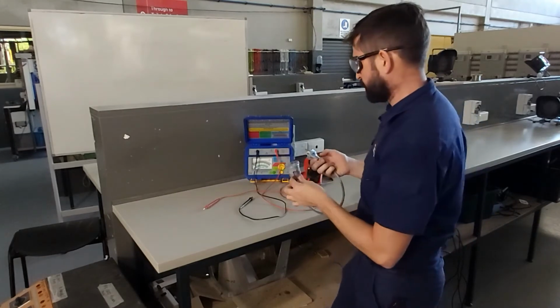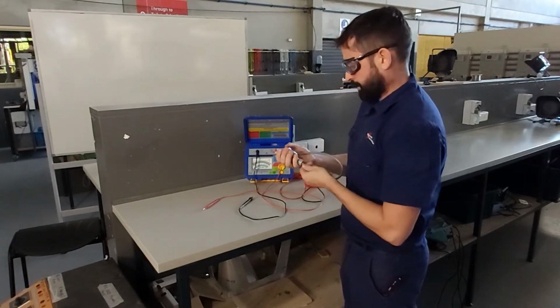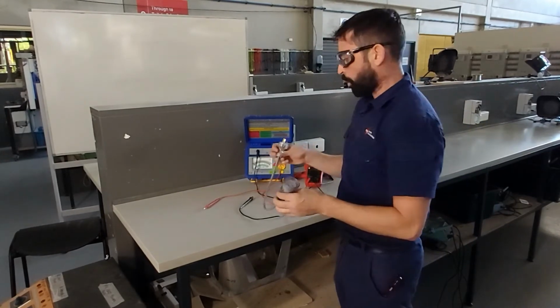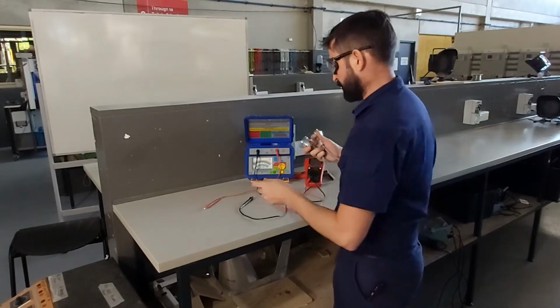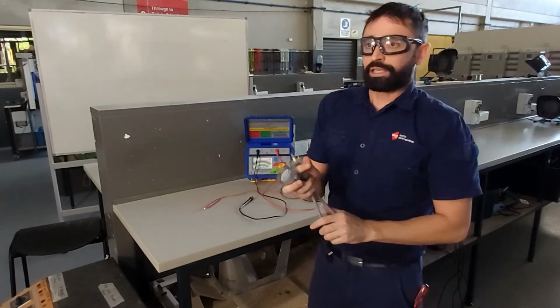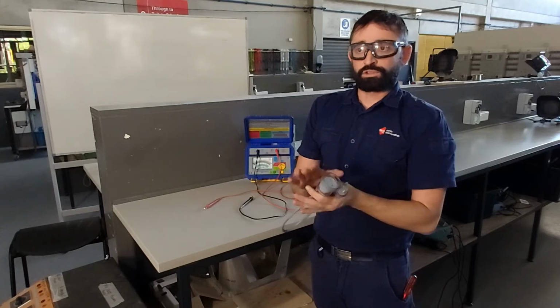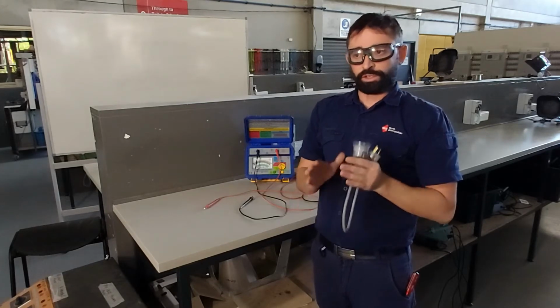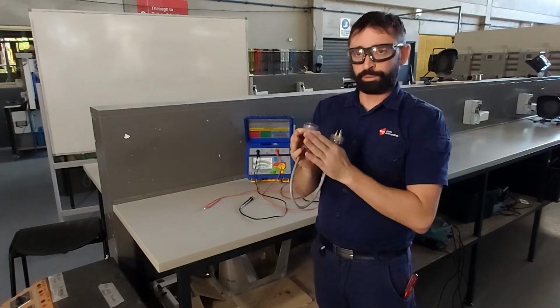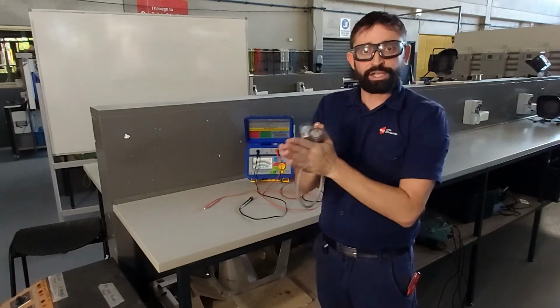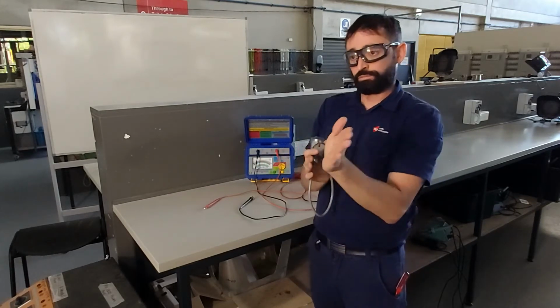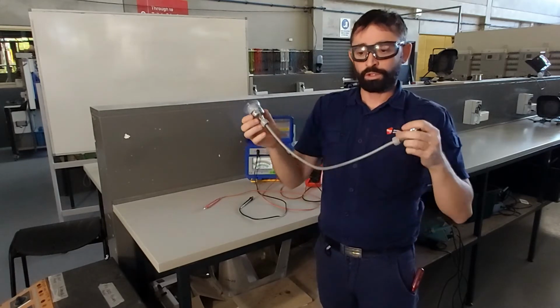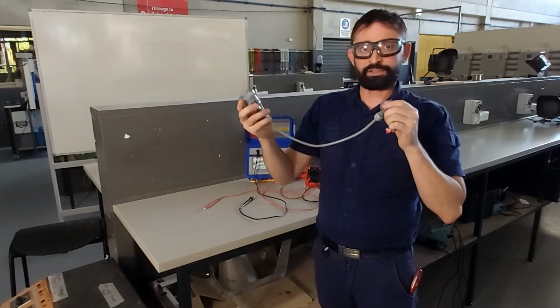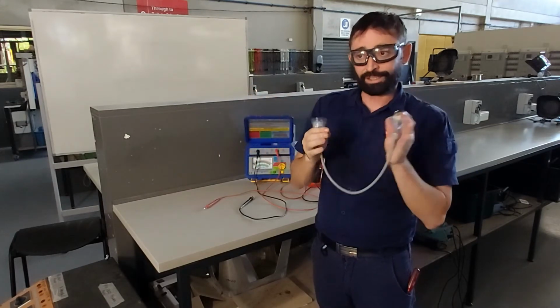Alright, the next test we're going to do is the insulation resistance test. What we're going to do here is check the insulation of all the active conductors down to earth. We want to make sure that the current's going to go where it needs to go. A bit like the plumbers doing an air pressure check on their pipes. They want to make sure the water doesn't start leaking out. Exactly what we're doing when we apply current to the active conductors. We want to make sure the current isn't going to leak out.